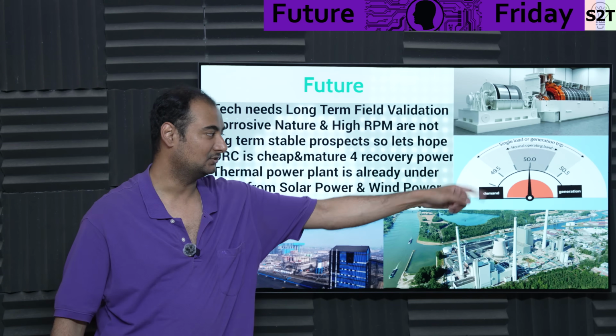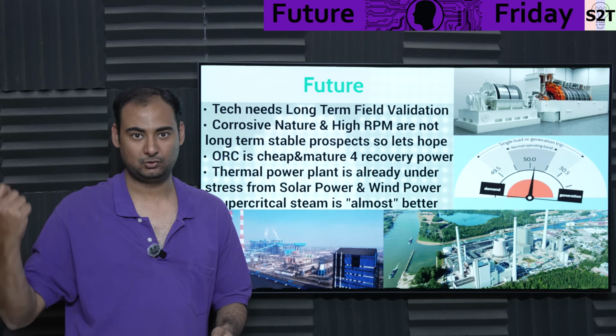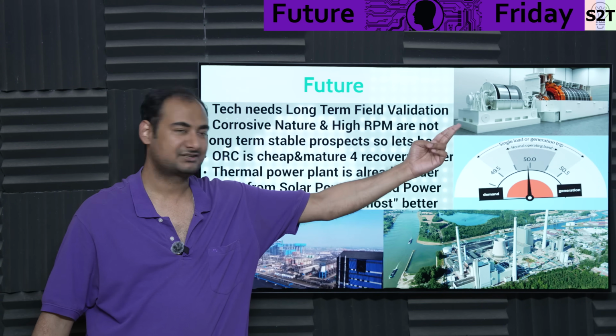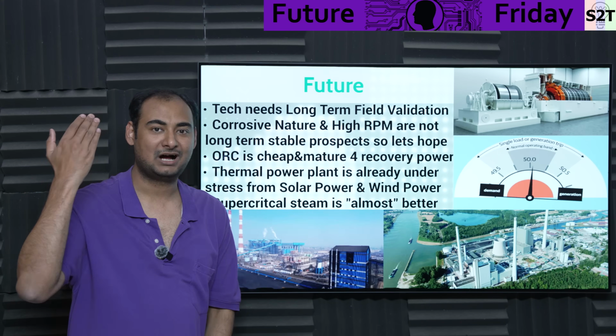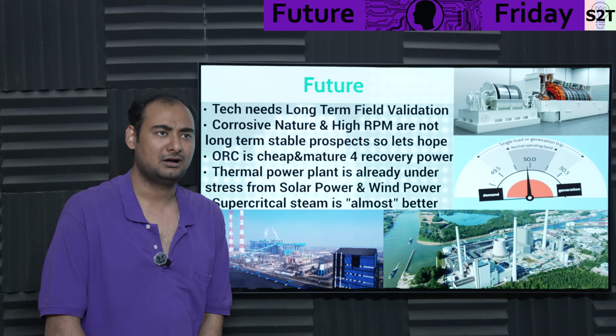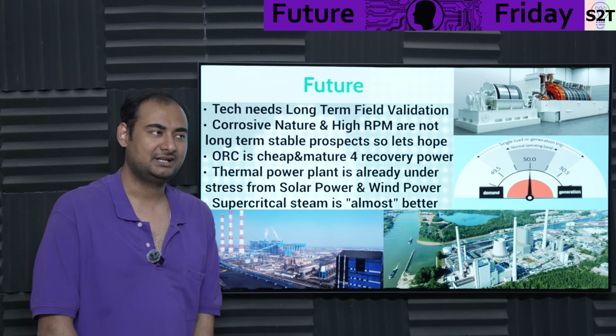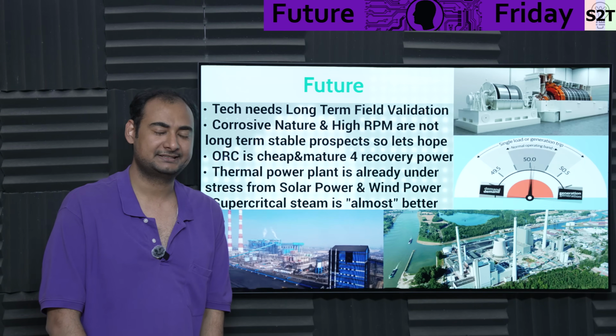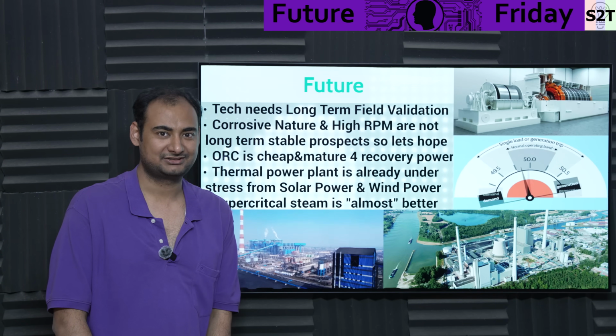Tada, your frequency starts to go up. What happens? Somebody disconnects the load - tada, your generation starts to bounce back. Again RPM will start to go high, and your steam system would be like, my RPM is supposed to be 3000, why the heck is it 3001? Why the heck is it 3005? Okay, shut down the steam pressure.